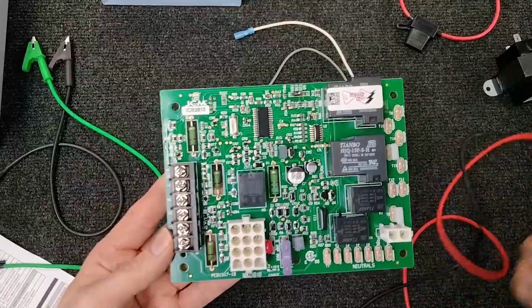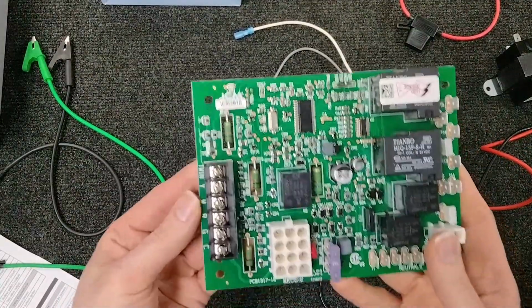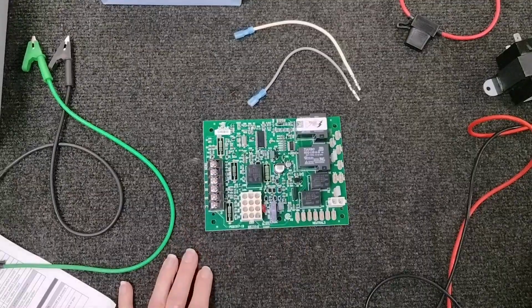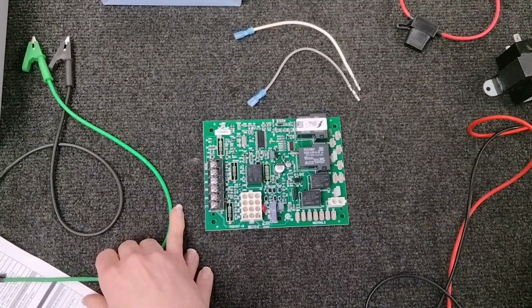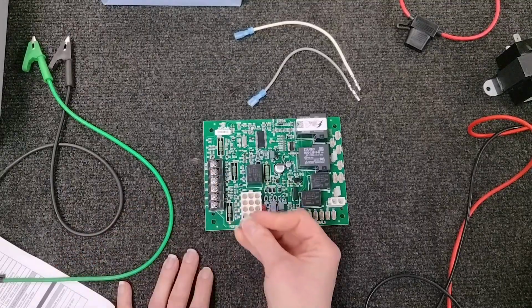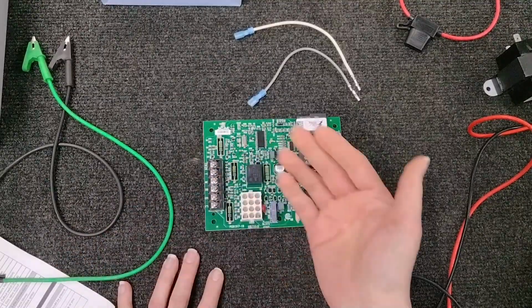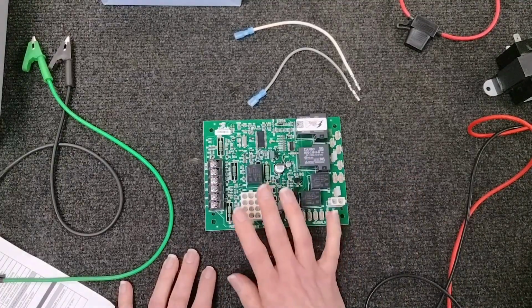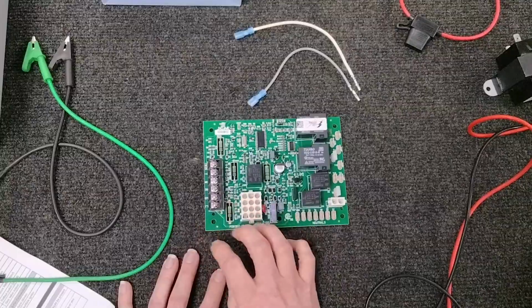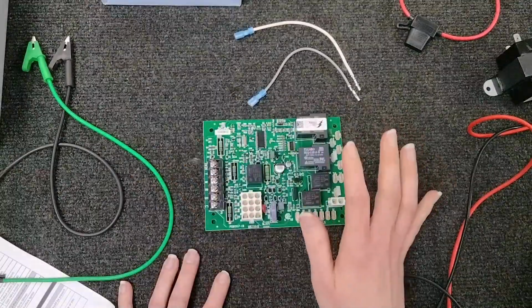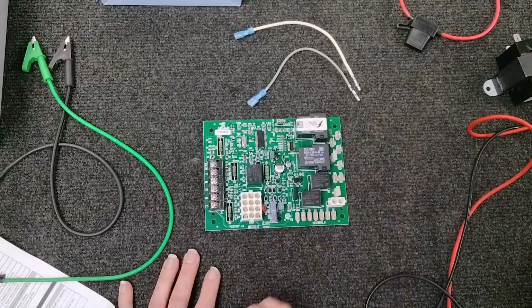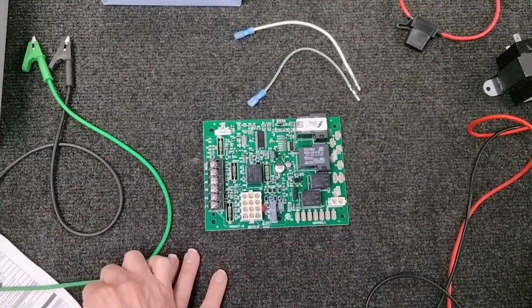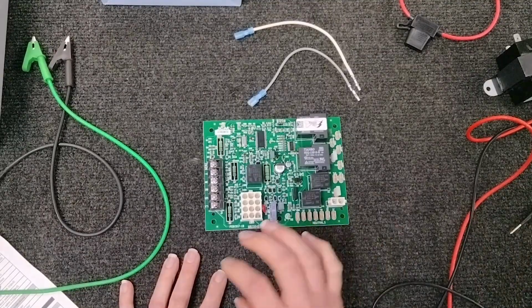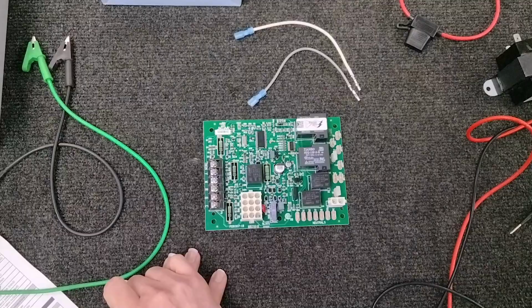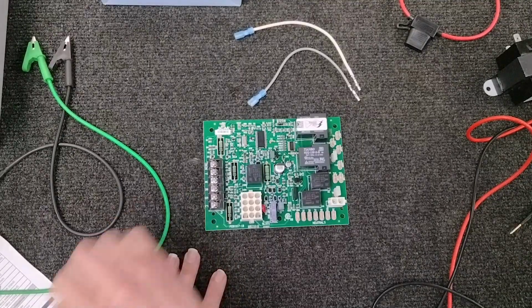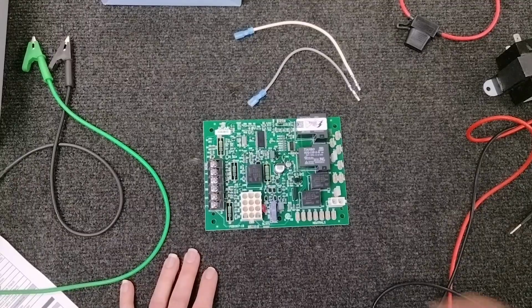You can also check on the R and Y if you're checking for cooling. So, to rule out the thermostat, you need to know the thermostat is actually sending the signal for the heat or the cool to come on. Now, the difference between heating and cooling is something we'll go into with this control board, because there's a difference when calling for cooling versus heat. We'll get into that when we start getting into our AC series. But for now, know that R and W should have the call from the thermostat for heat.